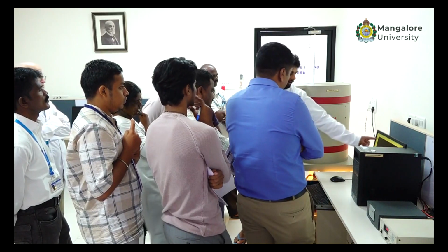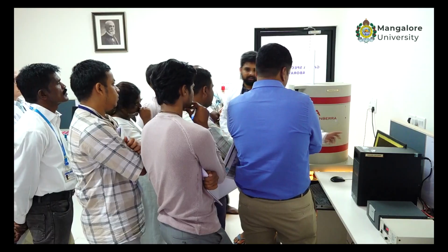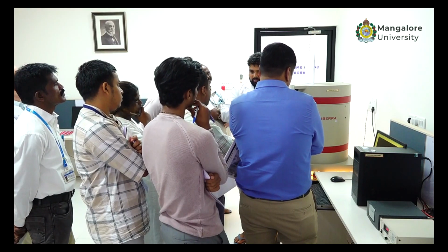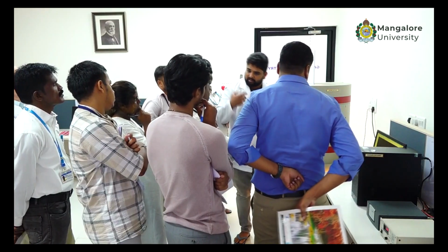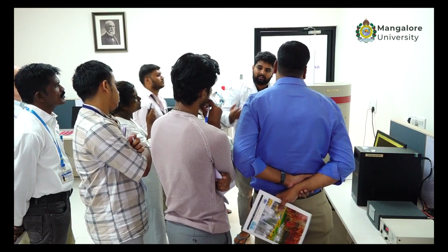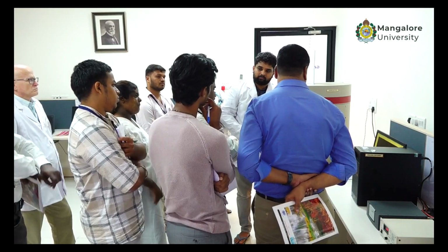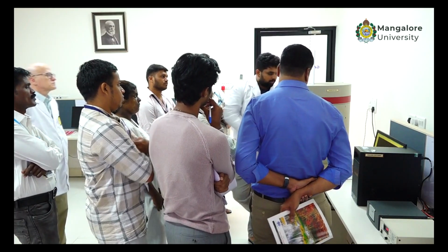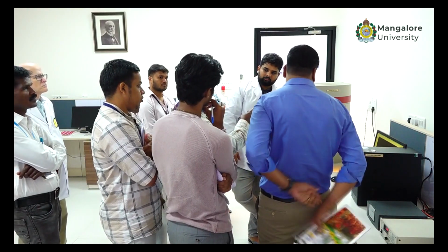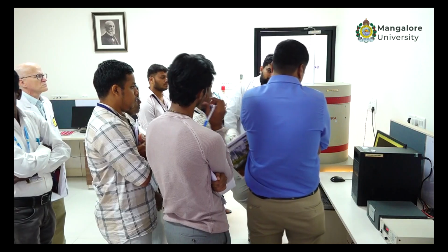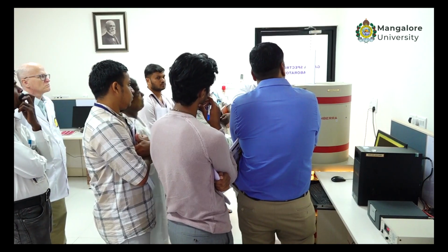Now, what is my counting time? Counting time is 60,000 seconds. Counts per second is calculated using this parameter, which depends on the sample. I can set it to 30,000. If the activity is high, I can set 10,000, 5,000, even 1,000 or 100 seconds. If you set 10,000 instead of 60,000, you might not get this big peak. Is there any difference with respect to the centroid? No, it might be the same, but you have to get a proper peak.